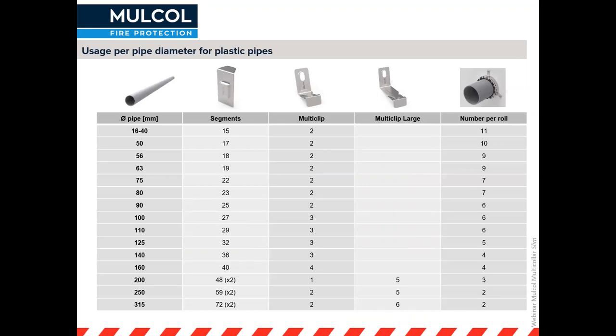The Multicollar Slim can be used for pipes from 16 millimeters all the way up to 315 millimeters. This table can be found on the back of the box and in the technical data sheets. For example, a 110 millimeter pipe needs 29 segments and three multi-clips to fix the Multicolor to the wall, which means you can get exactly six Multicolor Slims for 110 millimeter pipes out of one roll.